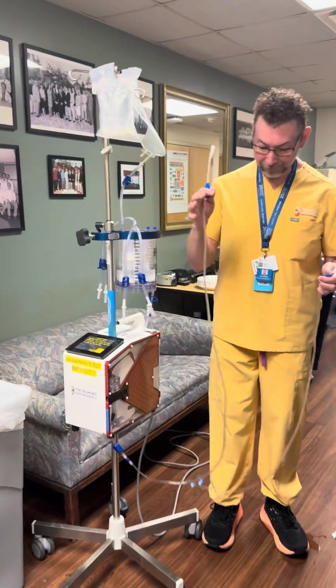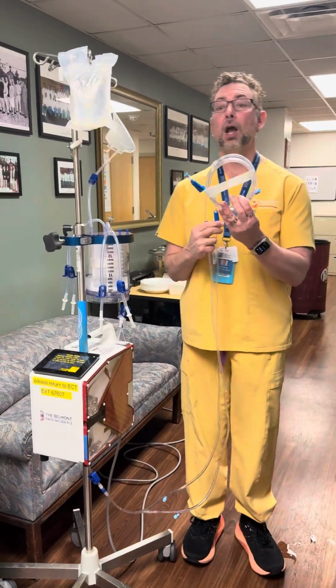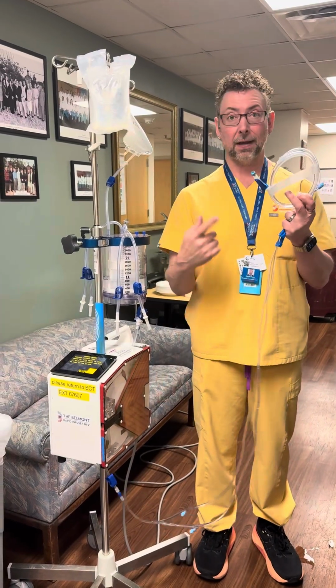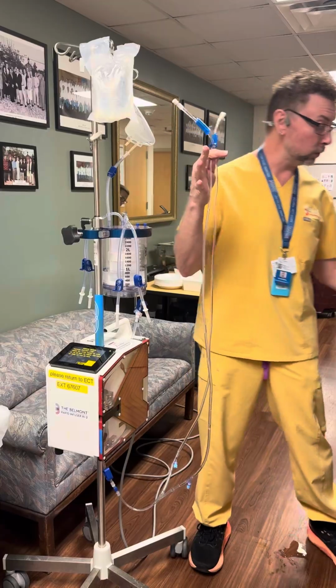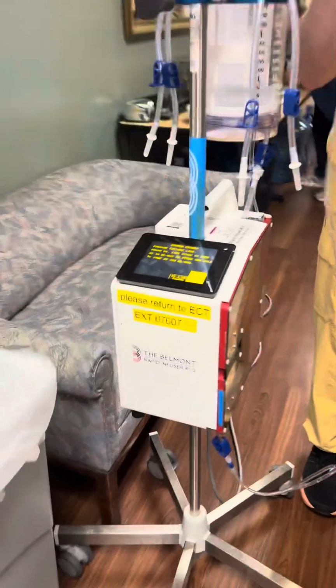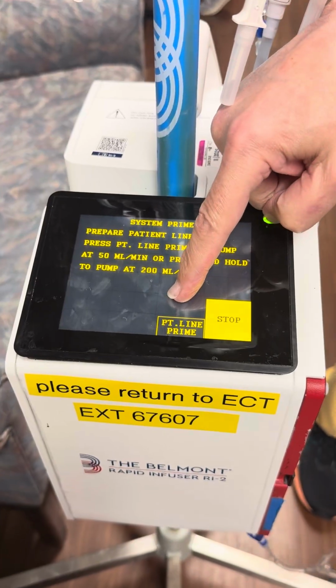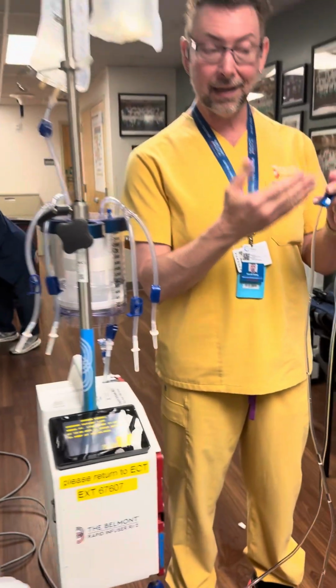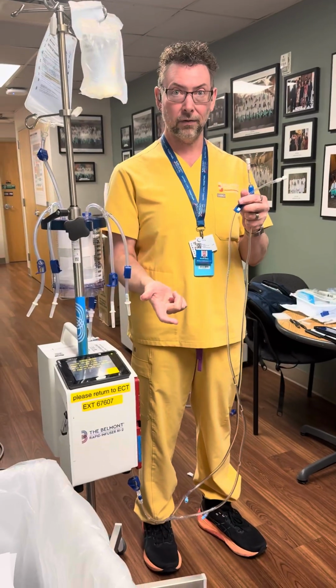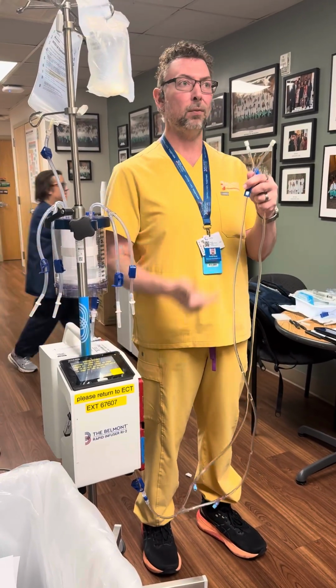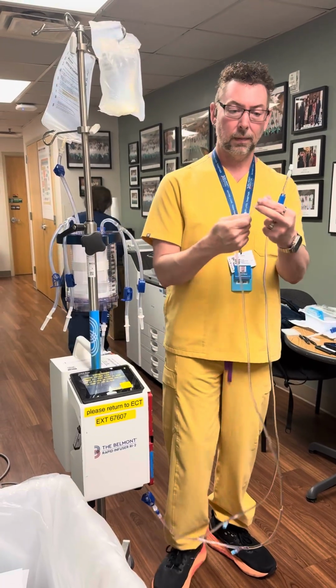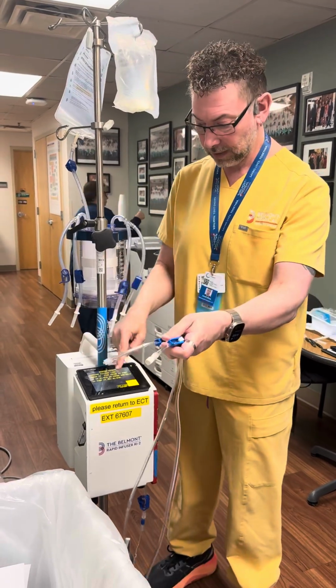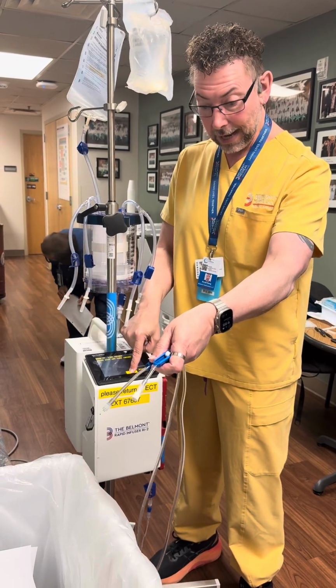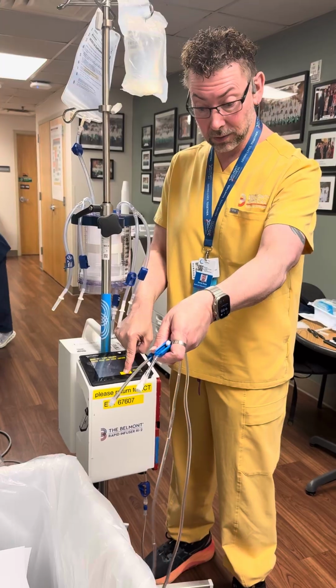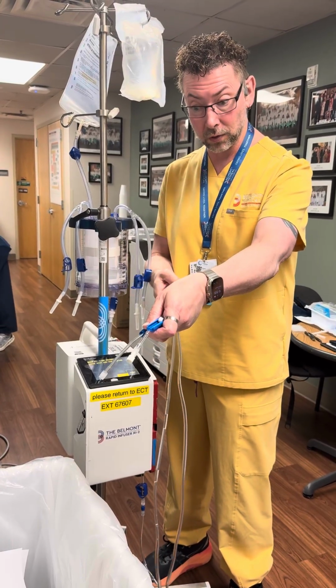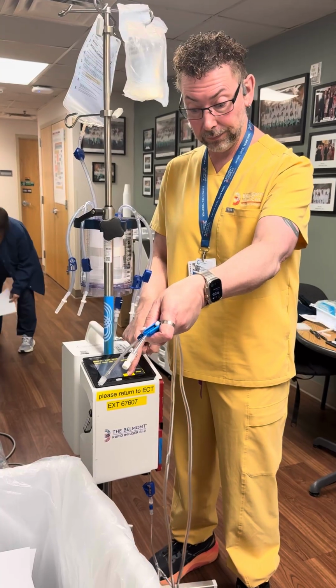Okay, so if you are using just the single limb, you're just priming directly into a trash can. You don't have to worry about doing them one side at a time. But if you're using the bifurcated line, you're going to want to keep one side clamped off, press and hold the patient line prime button, clear the air from one side, then clamp it off, open the other side and clear the air from it. If you're trying to do both of them at the same time, you always end up with air pulling back on one side. So you would just take the little cap off, aim it, press and hold the button. If you hold the button, it primes the line at 200 milliliters a minute. If you let go of the key, it slows down to 1/4 the speed. So hold the button and get the air out.